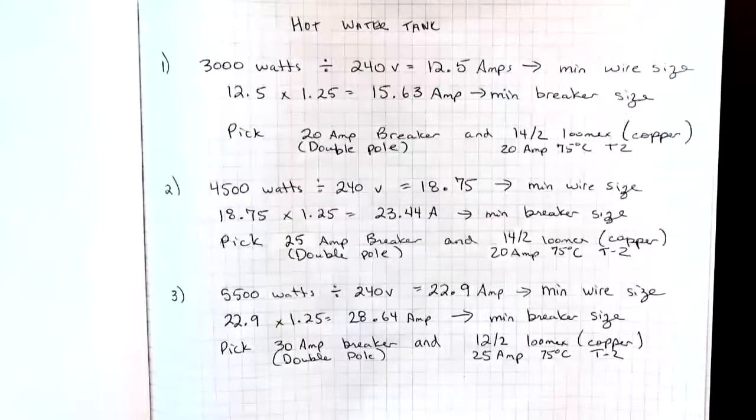3000 watts divided by 240 volts equals 12.5 amps. That is going to be our minimum wire size so that our ampacity of our wire is not less than our load.